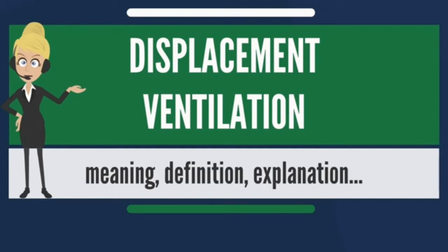The cool air accelerates because of the buoyancy force, spreads in a thin layer over the floor, reaching a relatively high velocity before rising due to heat exchange with heat sources, for example, occupants, computers, lights. Absorbing the heat from heat sources, the cold air becomes warmer and less dense. The density difference between cold air and warm air creates upward convective flows known as thermal plumes.